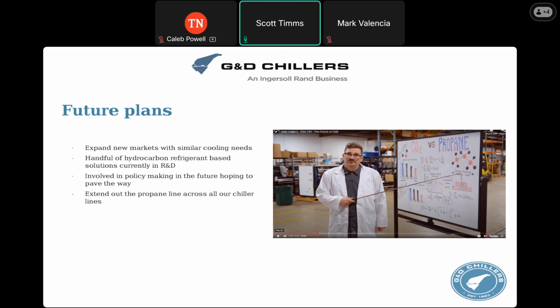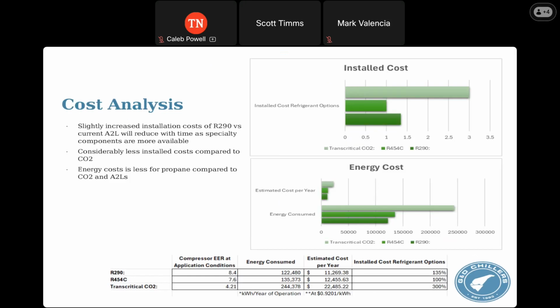On to the cost analysis for this specific project. R290 is a little bit more expensive to install than your standard A2L, essentially because of the safety features we have to put into place - leak detectors, that fan that pulls air through, and at the installation site itself you need to run a little bit of piping and ducting away from the unit to a safe space. So there is a little bit increased cost compared to the A2L options.